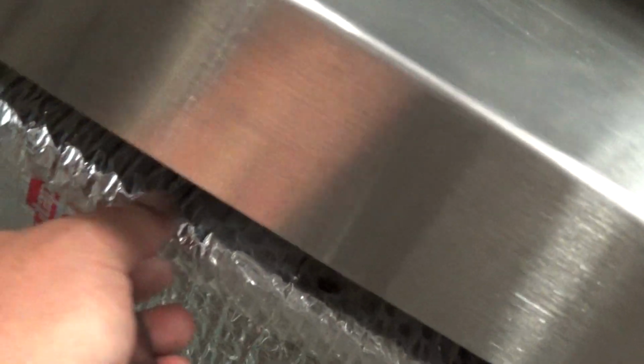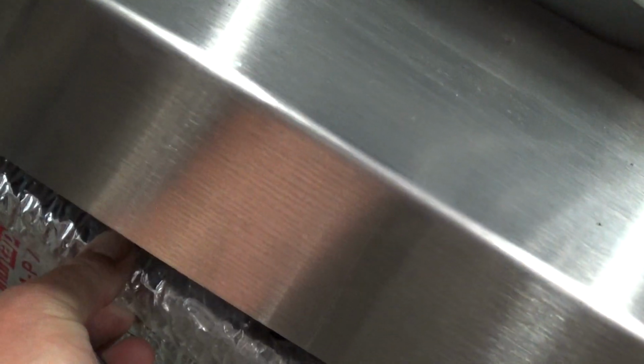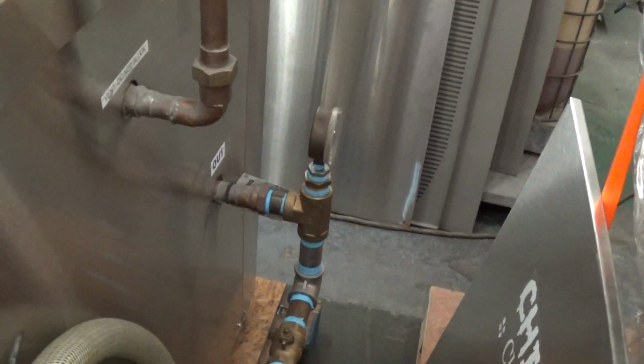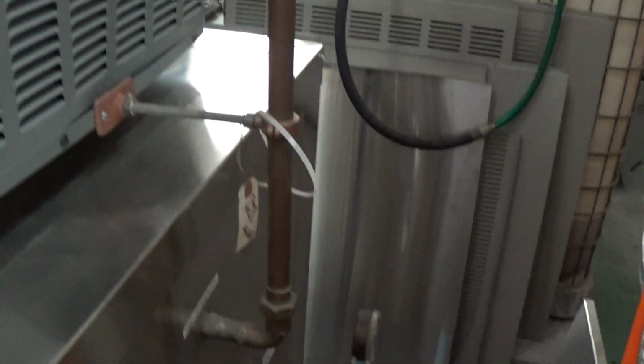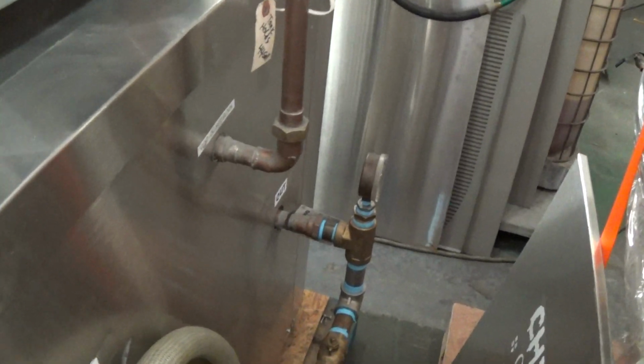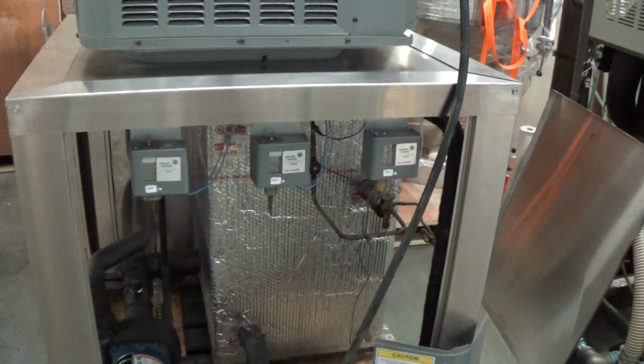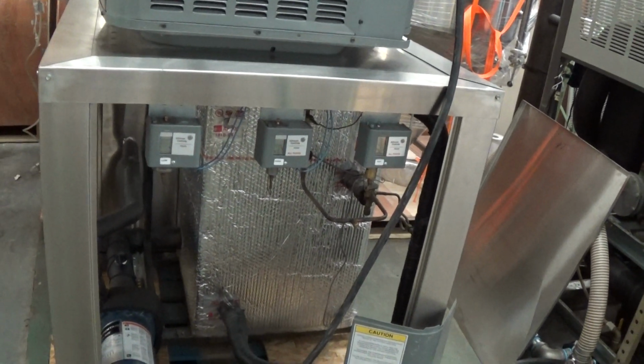So the tank has a lid. It is bolted on. The bolts are on the perimeter, but for testing, we have it unbolted. It also has a vent. You may want to just fill it through the lid, or you can fill it through this vent, where the prior user put this little copper tube. But keep in mind, it's not a sealed, pressurized loop. So if you overfill the tank, it's going to start leaking out through that lid. Just be careful of that.